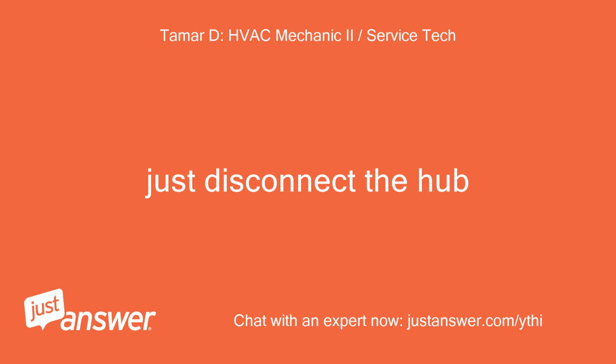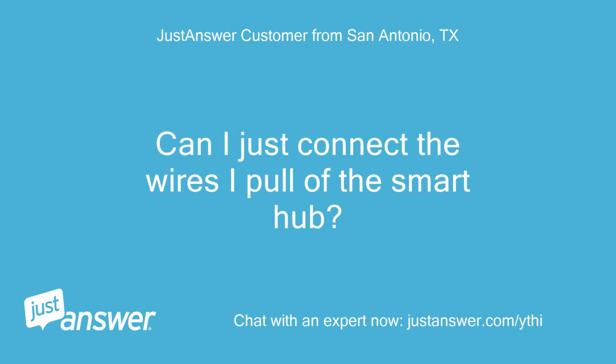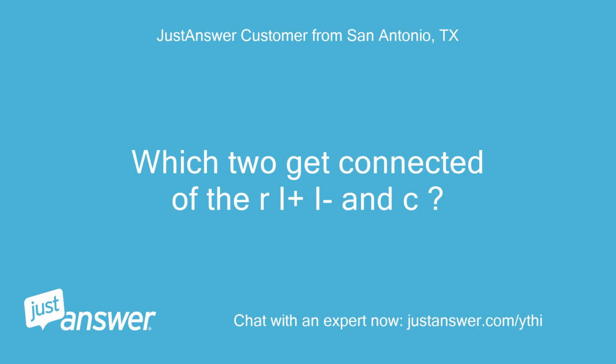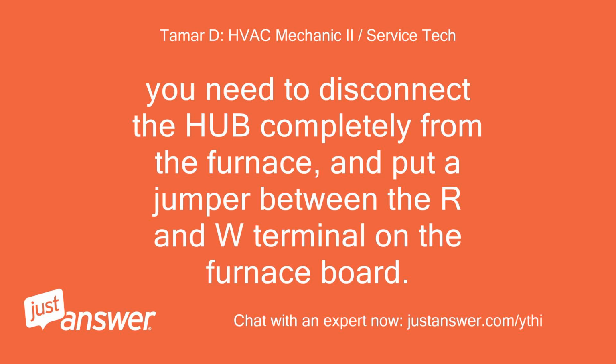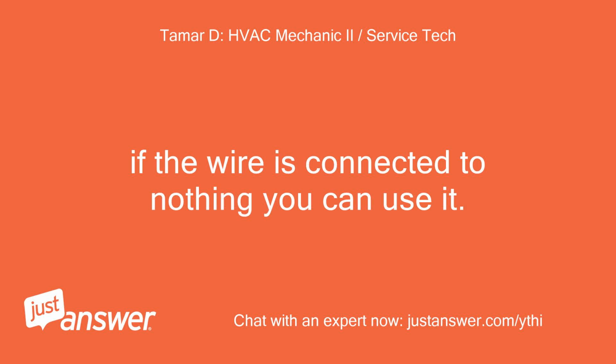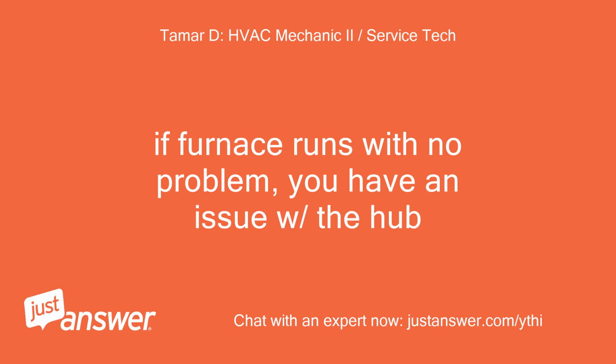Just disconnect the hub from the furnace temporarily. Can I just connect the wires I pulled off the smart hub? Which two get connected of the R, I+, I-, and C? Cannot. You need to disconnect the hub completely from the furnace, and put a jumper between the R and W terminal on the furnace board. If the wire is connected to nothing, you can use it. If it's connected to something, you can't. If the furnace runs with no problem, you have an issue with the hub.